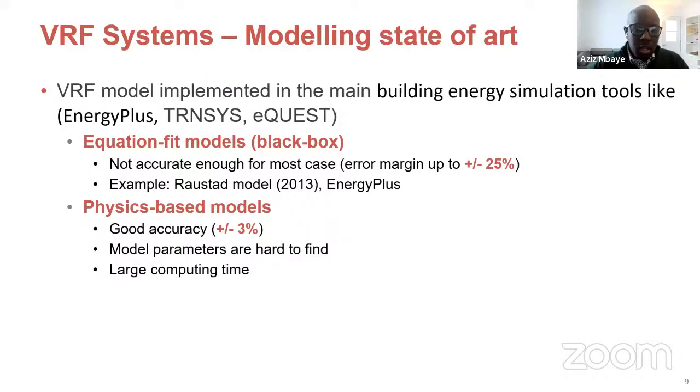Regarding the physics-based models, they use, most of the time, first principle equations to describe the behavior of the VRF, which is why they are more accurate in predicting the performance of the system, but they require knowledge of the model parameters, which is not an easy task, especially for commercial units where we do not have inside information of the system. And due to their complexity, they can be very computationally expensive, making it difficult if you want to simulate a system with up to 100 indoor units.